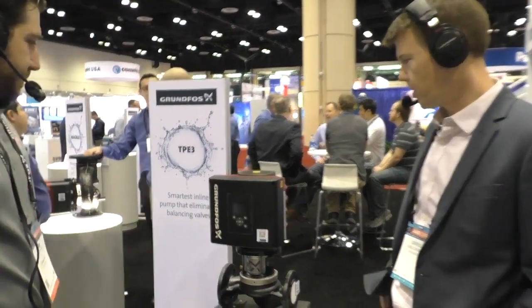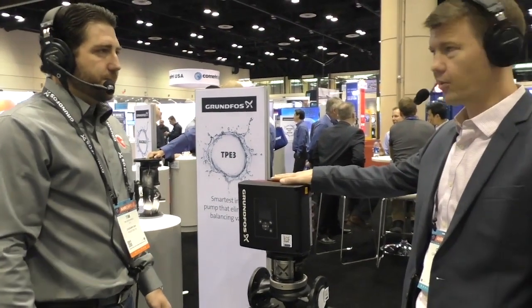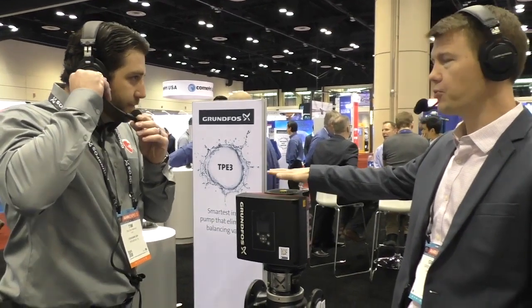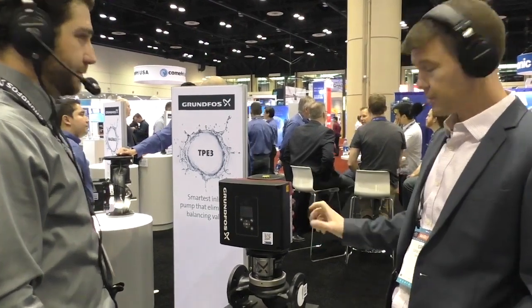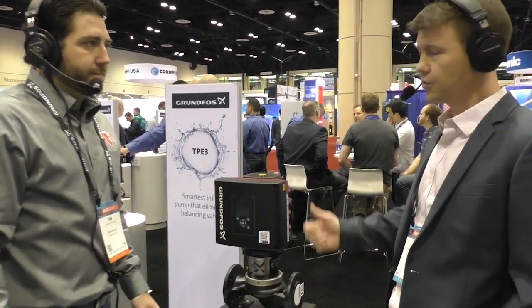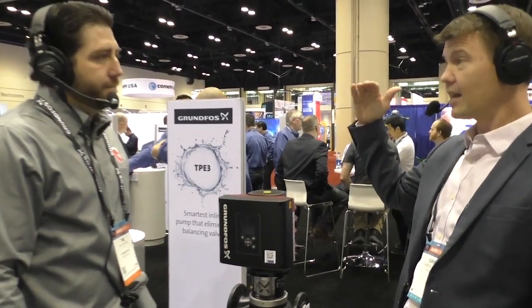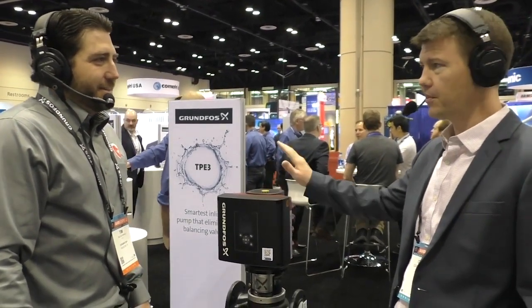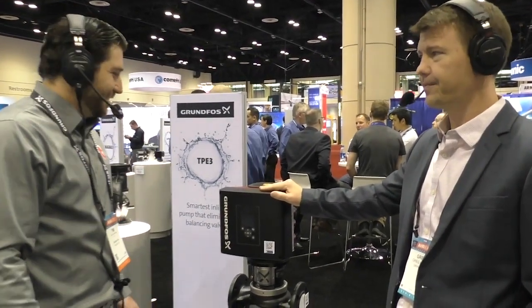Yeah, no, this is a great little pump. The main reason we're able to achieve those kinds of efficiencies is because we have our ECM motor technology integrated with all of them. And what that allows us to do is to overspeed this motor at really high RPMs, which gets to the specific speed of this specific hydraulic pump, which gets super high efficiency. So the hydraulic DOE PEI limit is 1.0, with lower number being better. Yep. This is in the 0.2 range. Right. Most efficient pump out there. Yeah, meaning it's 80% better than the bar. Right? Absolutely. Yeah. Yep. No, it's a great pump.